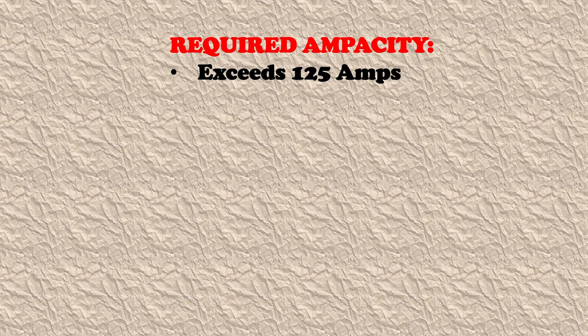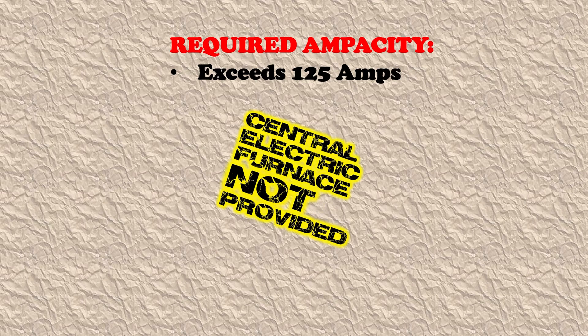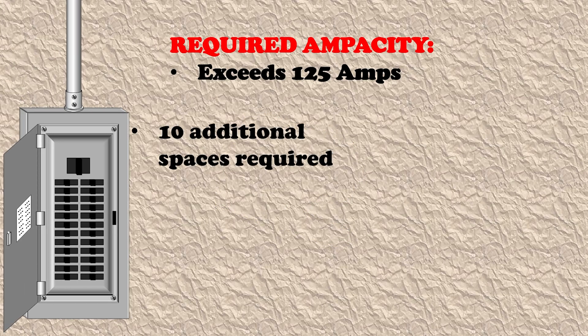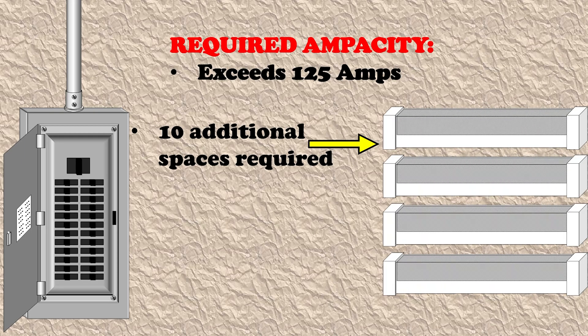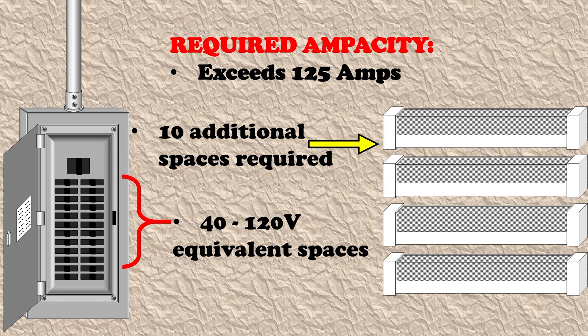Our final example: we exceed 125 amps and a central electric furnace is not provided. As in the previous example where we did not have an electric furnace provided, we're going to require extra space again in the panel. Because we're above 125 amps, we're going to require an additional 10 spaces for baseboard heaters or whatever other method of heating we have that is not a central electric furnace — meaning we're taking up more panel space to heat our dwelling unit. In this case, we are required to have 40 120-volt equivalent spaces.